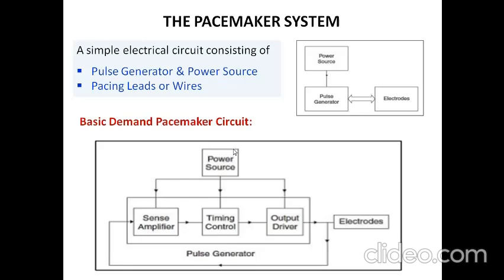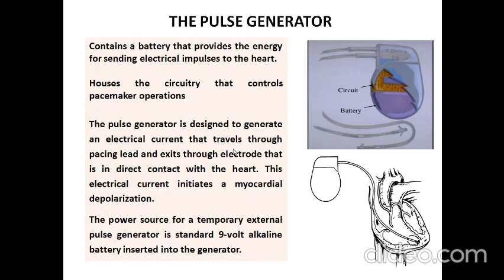It has only three parts: a power source, a pulse generator, and electrodes. This is a very simple circuit analysis of a pacemaker. The pulse generator contains a battery that provides energy for sending electrical impulses to the heart. It houses the circuitry that controls pacemaker operations. The pulse generator is designed to generate an electrical current that travels through the pacing leads and exits through electrodes in direct contact with the heart. This electrical current initiates myocardial depolarization. The power source for a temporary external pulse generator is a standard 9 volt alkaline battery inserted into the generator. It is the common external pacemaker that we use.